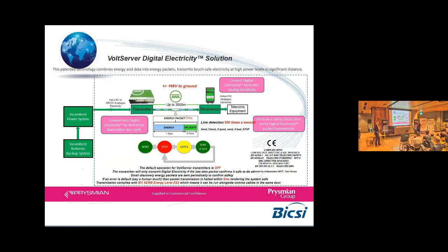Now, to deliver 2,000 watts down 2 kilometers, you need approximately a 3.5 cable. It's not a standard instrumentation cable. You have to worry about the capacitance between pairs and between the shield. So it's got to meet certain specifications.